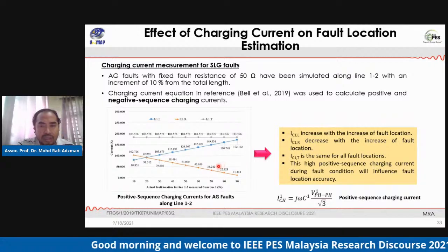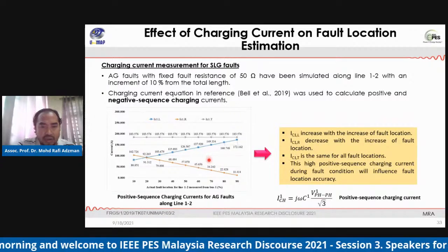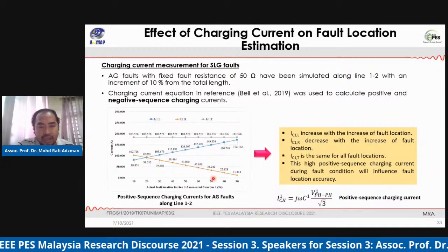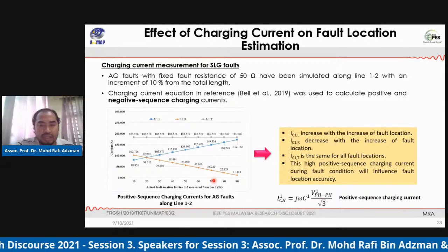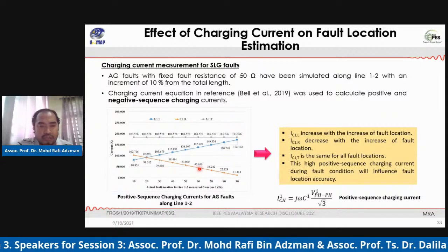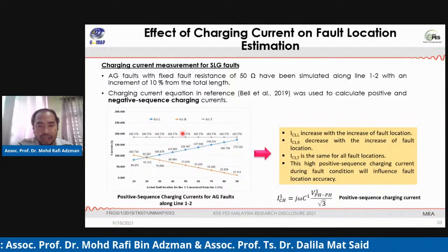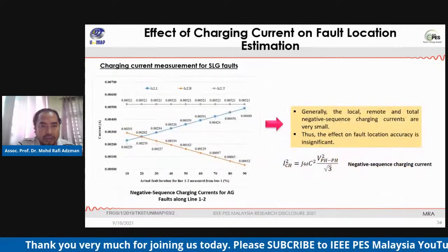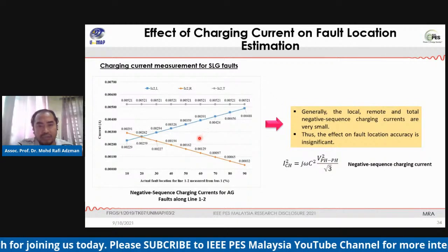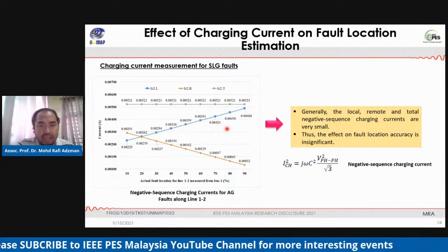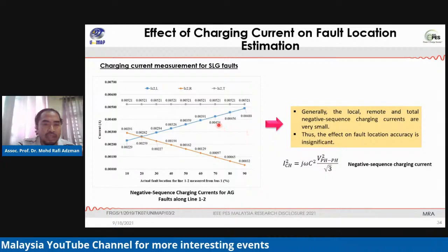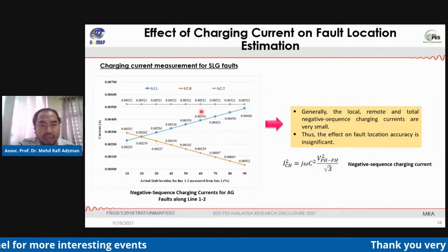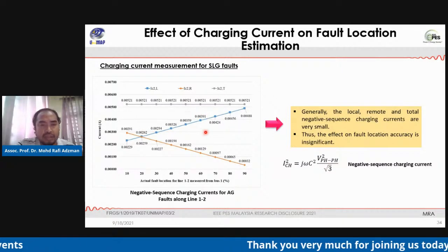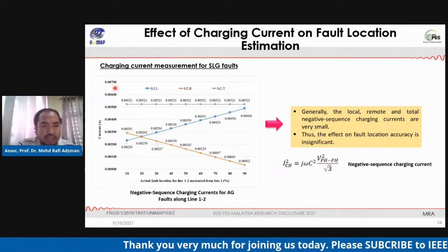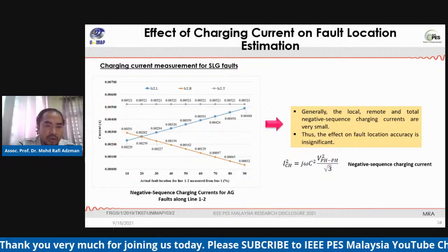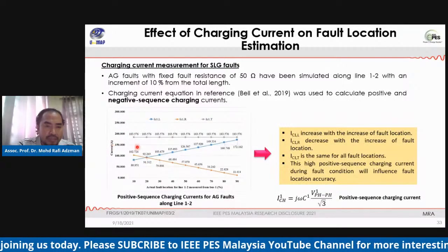Okay, and the total charging current is the same for all fault locations. This high positive sequence charging current during the fault condition will influence the fault location accuracy for the positive sequence fault location technique. While for the negative sequence fault location technique, we can see that there is less effect on the fault location accuracy, and it can be assumed that the charging current is insignificant to the effect on the fault location itself. So you can see that the current is small compared to this one, okay, positive sequence.